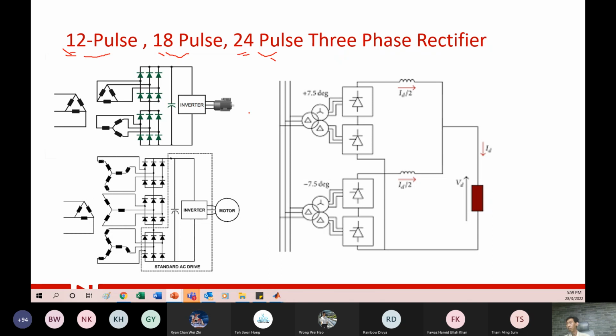So there are only two ways to settle this harmonic problem. Either you solve it at the grid side, or you solve it at the power electronic side. On the power electronic side, you have to increase the pulse number. The problem is that the converter becomes very expensive because you double the bridge, so the price doubles. And you are going to use a transformer anyway, so instead of a single winding, you need a double winding. From 6 to 12, you almost literally double your price. If you go to 18, even more, and then the fourth one, 24.